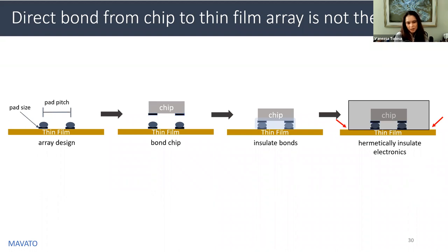And then lastly, you have to find a way to hermetically encapsulate the electronics from the environment. This is what's tricky with this design, because the other end of this thin film is the electrode array that's implanted into tissue, and fluid will travel up the cables and get to this interface that I pointed to in red. Without spending more time on this, I'll just leave it as a failure point for really long-term implants.